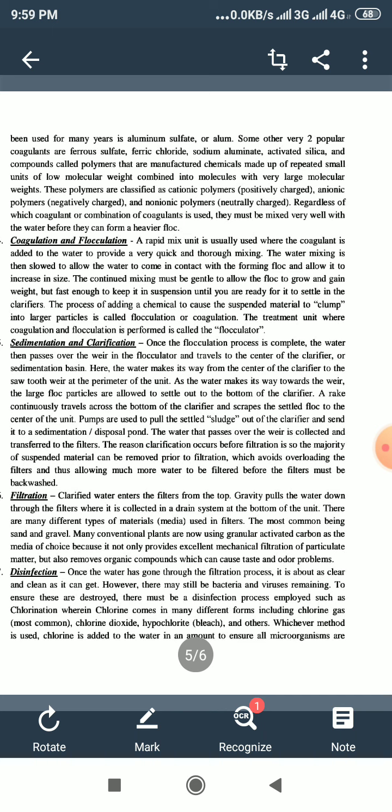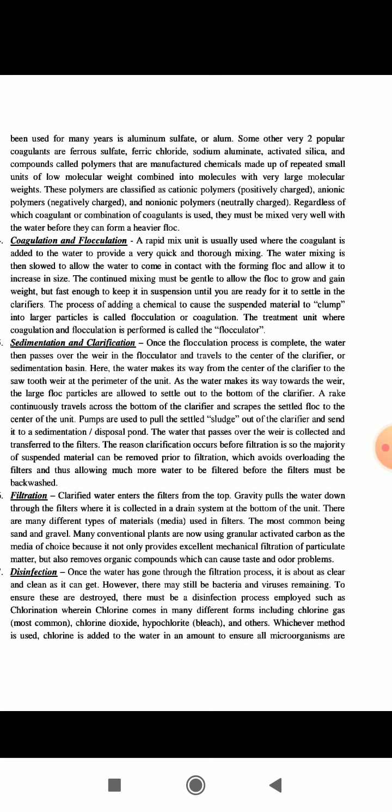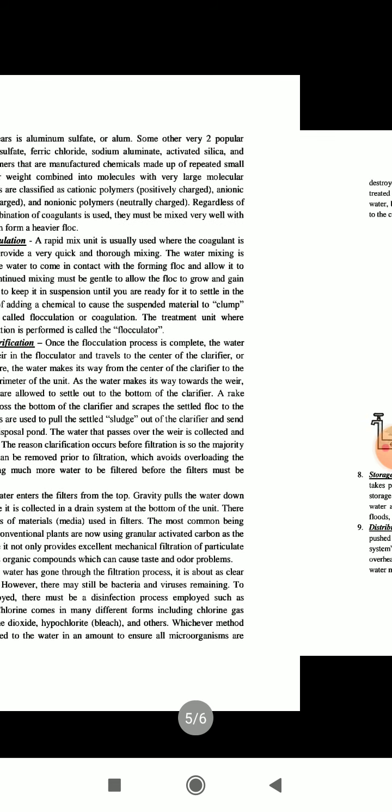Next is disinfection. Once the water has gone through the filtration process, it is about as clear and clean as it can get. However, there may still be bacteria and viruses remaining. To ensure these are destroyed, there must be a disinfection process employed such as chlorination, where chlorine comes in many different forms including chlorine gas (most common), chlorine dioxide, hypochlorite bleach, and others. Whichever method is used, chlorine is added to the water in an amount to ensure all microorganisms are destroyed.